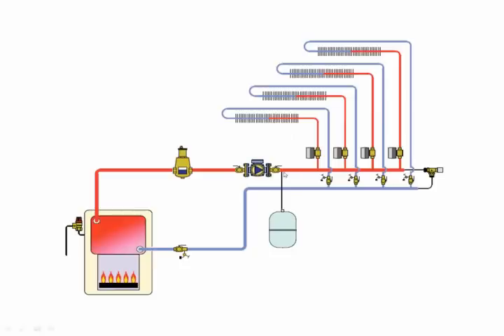Well, let's say the starting pressure of the expansion tank in your system was 20 psi. Nothing's turned on, and you put in 20 psi. And this pump is capable of generating a 30 psi head. The expansion tank is going to maintain 20 psi, and that pump's going to generate 30 psi, which will do what? What does that cause? Well, it's going to create a vacuum on the backside of this pump. Air separators such as Caleffi's or anyone else's work under positive pressure. So as air bubbles accumulate, rather than being vented out, if we got negative pressure, we'll suck air in and cause a problem with the pump, okay? At worst, it airlocks and fails if it doesn't have any temperature protection device. So a better place to put it is behind the pump.